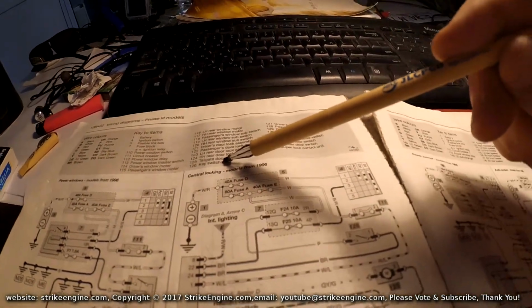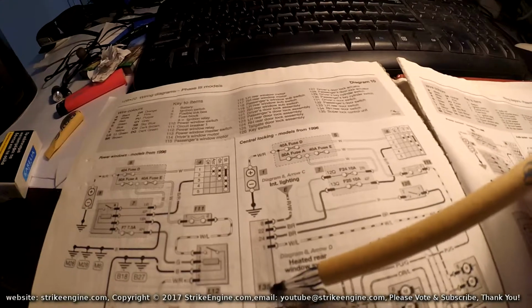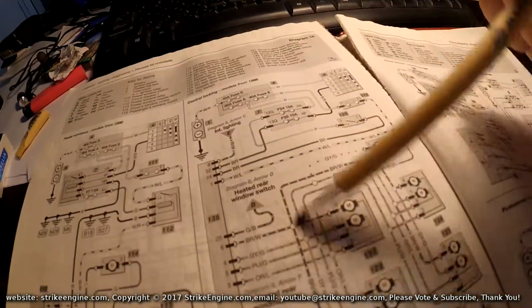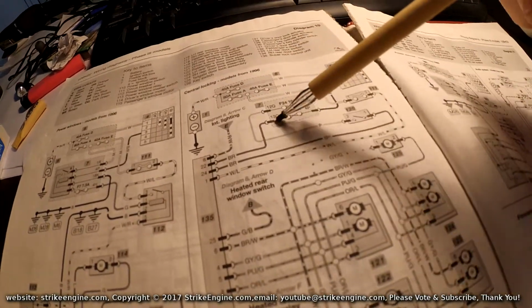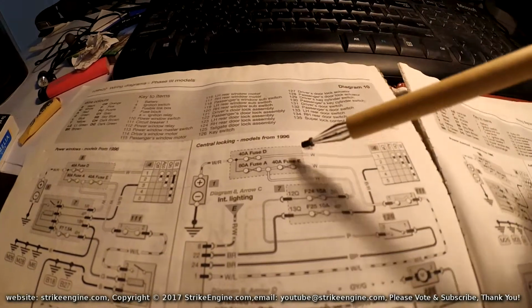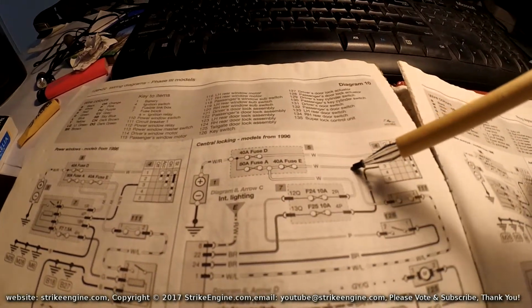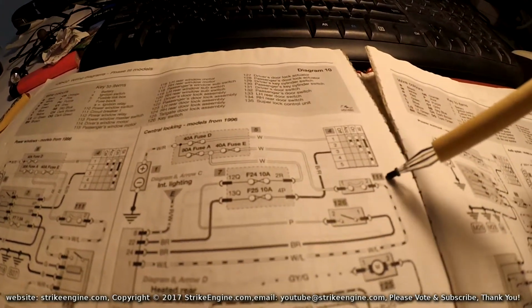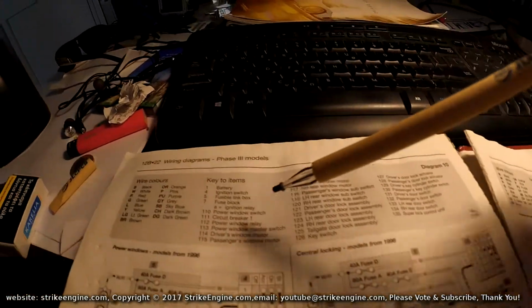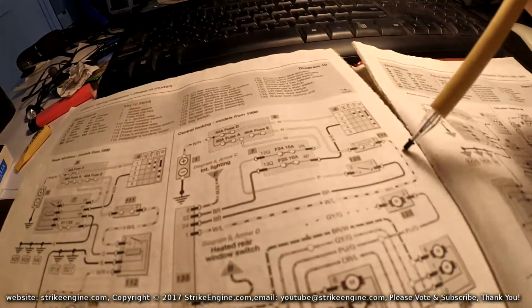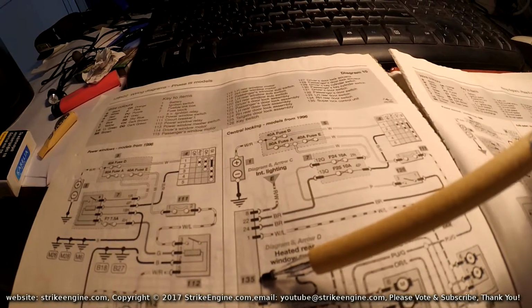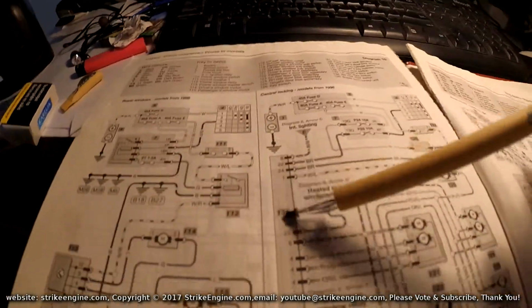126 is the key switch, and then it goes into 135, which is a super lock unit. So it's not this one — this has got nothing to do with it. However, we've got this one here, 40 amp fuse, which goes to 111, which is the circuit breaker, which then goes into the super lock unit 135.